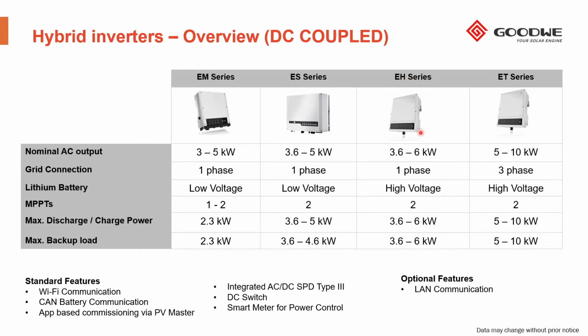Moving along to the EH series, this is also a single phase inverter. It's available from 3.6 to 6 kilowatts. It is a high voltage inverter, so this is batteries from around 180 to 600 volts. They have 2 MPPTs. The max discharge and charge power is between 3.6 and 6 kilowatts, and the backup load is 3.6 to 6 kilowatts. The EM and ES series are older generation inverters that we've improved over the years, whereas the EH series is a brand new inverter which has just been released into the market and does have Synergrid approval as far as I understand. So ready to use in Belgium.